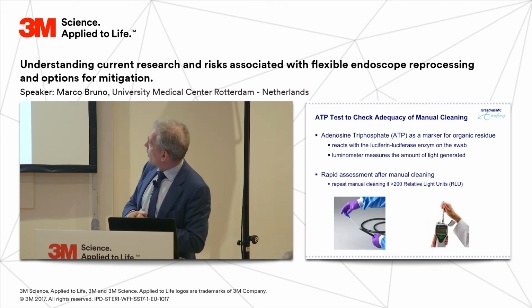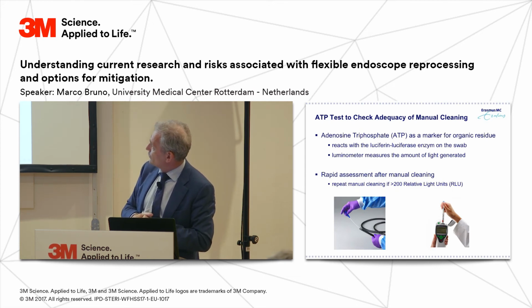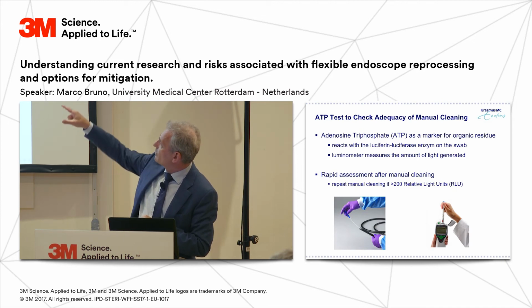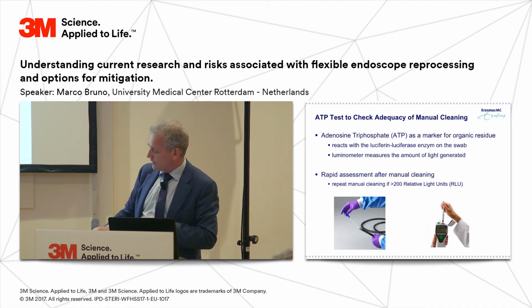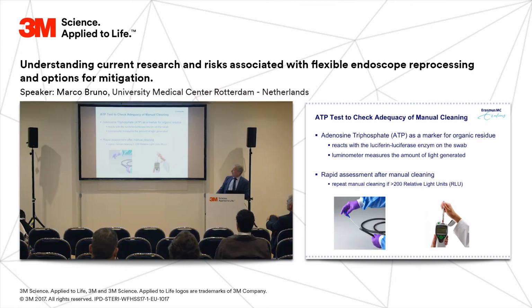The ATP test is a marker for organic residue. It reacts with luciferase enzyme on the swab, and you have a luminometer that measures the amount of light generated. And it works very quickly. You can do a very rapid test after the manual cleaning, and you have a certain threshold that you can read on the device. In the literature now, it's stated that a threshold of about 200 RLU is probably the threshold that one should use.